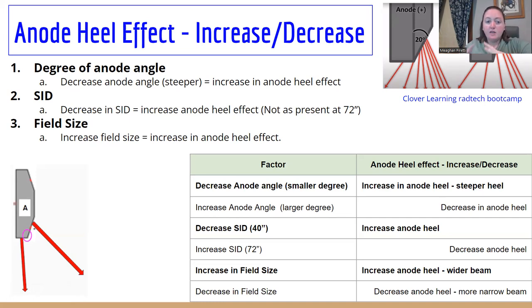And then field size, the larger the field size, the larger the anode heel effect, think wider beam, wider light field, more is going to get stolen from that anode.